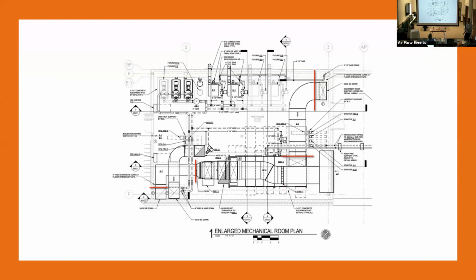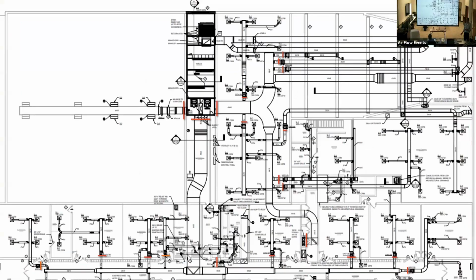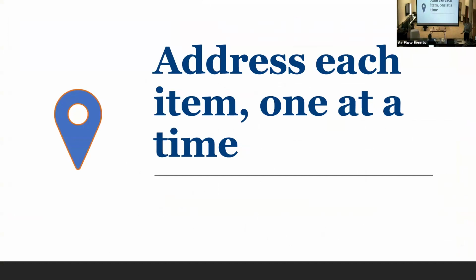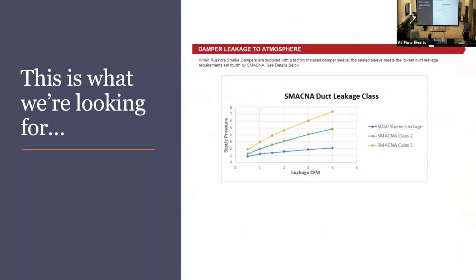And I'm gonna run this test right here and I gotta stop. Why do I have to stop? Because there's a fire smoke damper at the wall penetration where the shaft is, and I can only test this much ductwork. If that's an 8-story shaft, I gotta do another test on the return side, to get to 25%. I've got this little bit. So it is an epic pain in the butt. Figure out where you're gonna test if the fire smoke dampers leak. Look at that. And there's a lot of caps to get to 25%. Okay, so one at a time, we're gonna tackle this and I'm gonna turn it over to Mark.